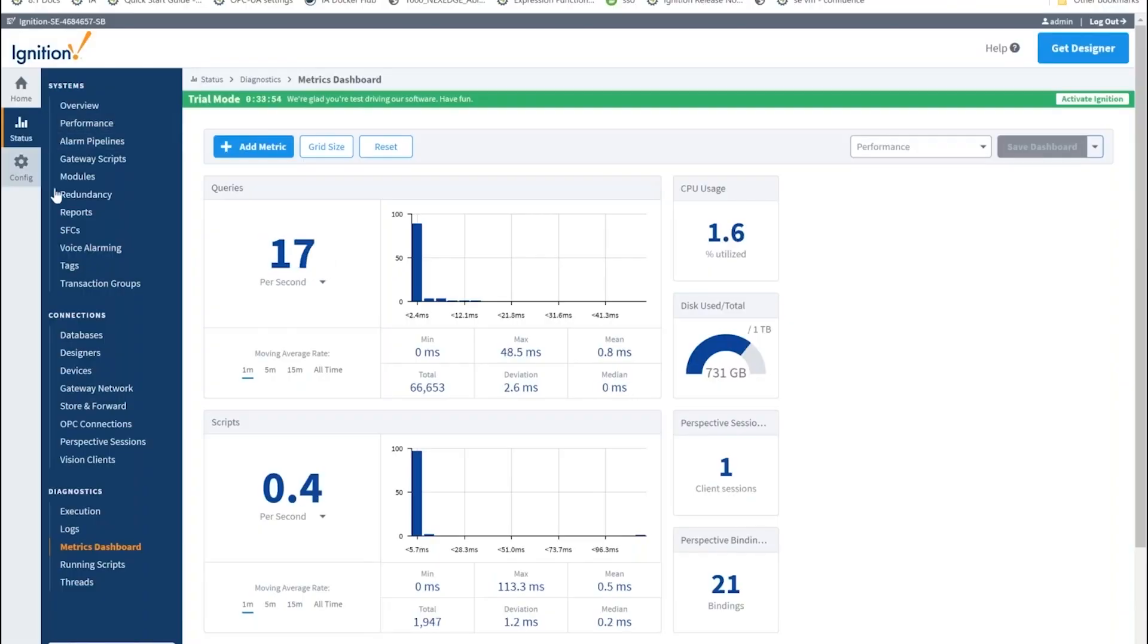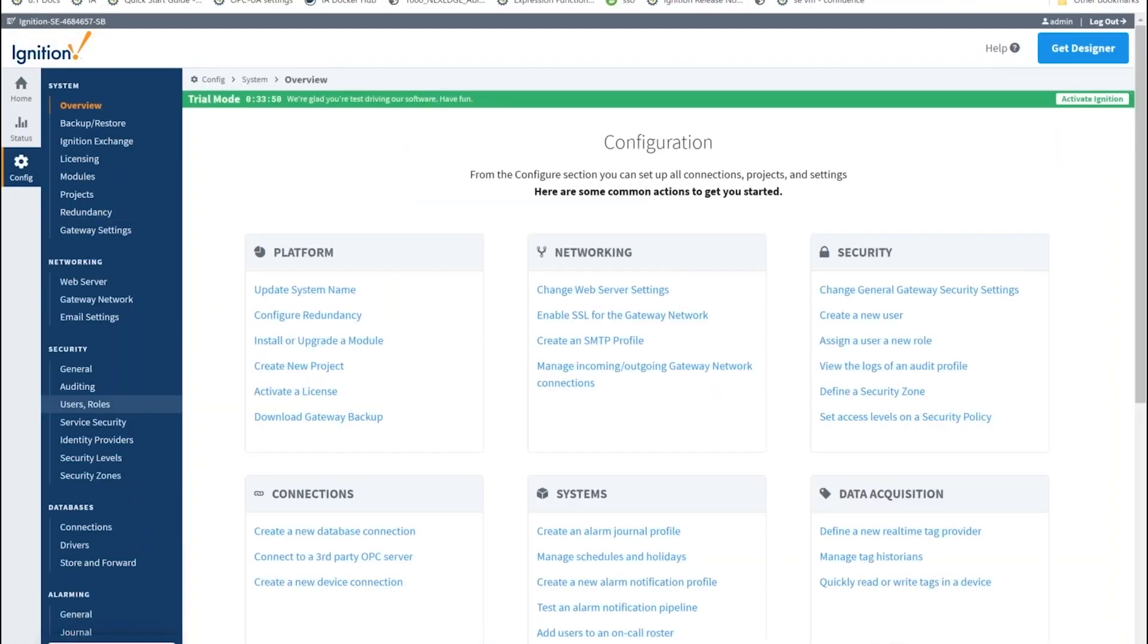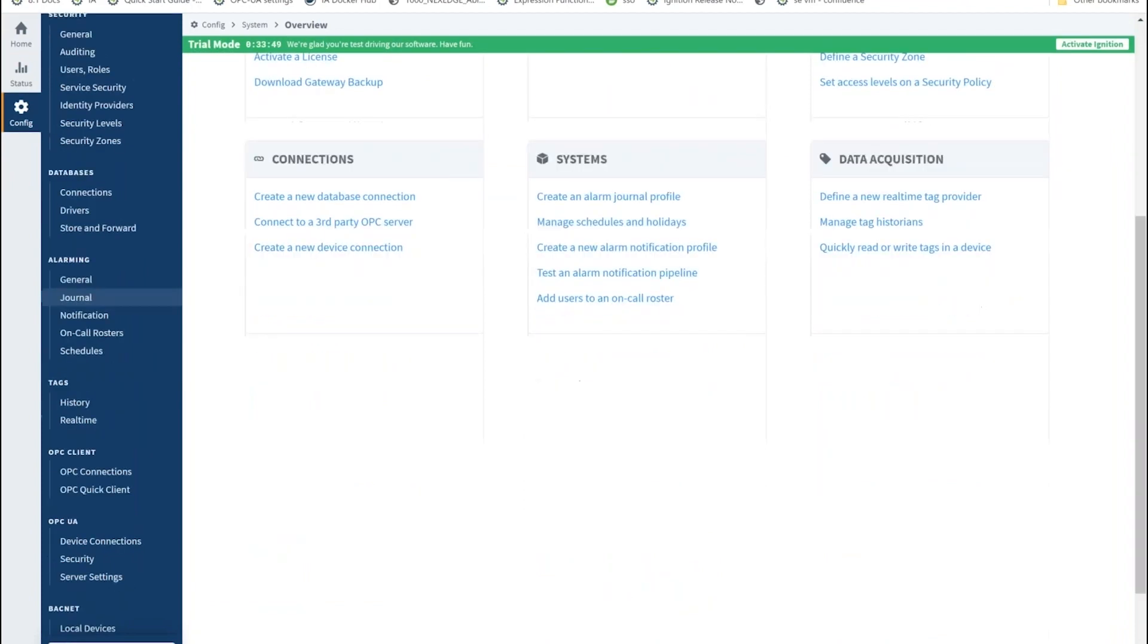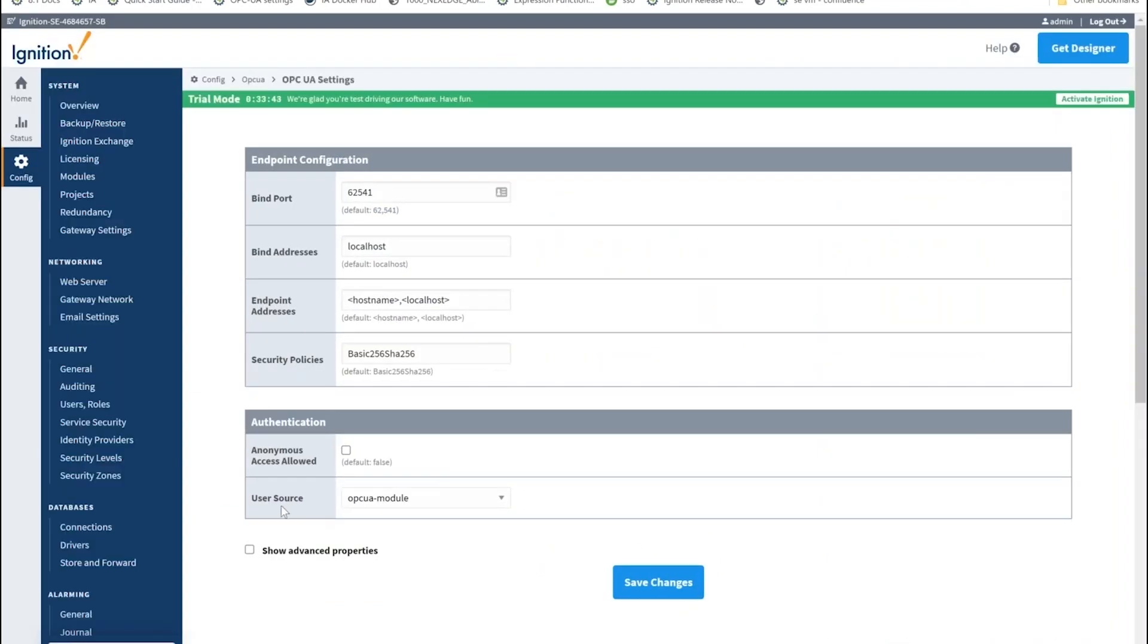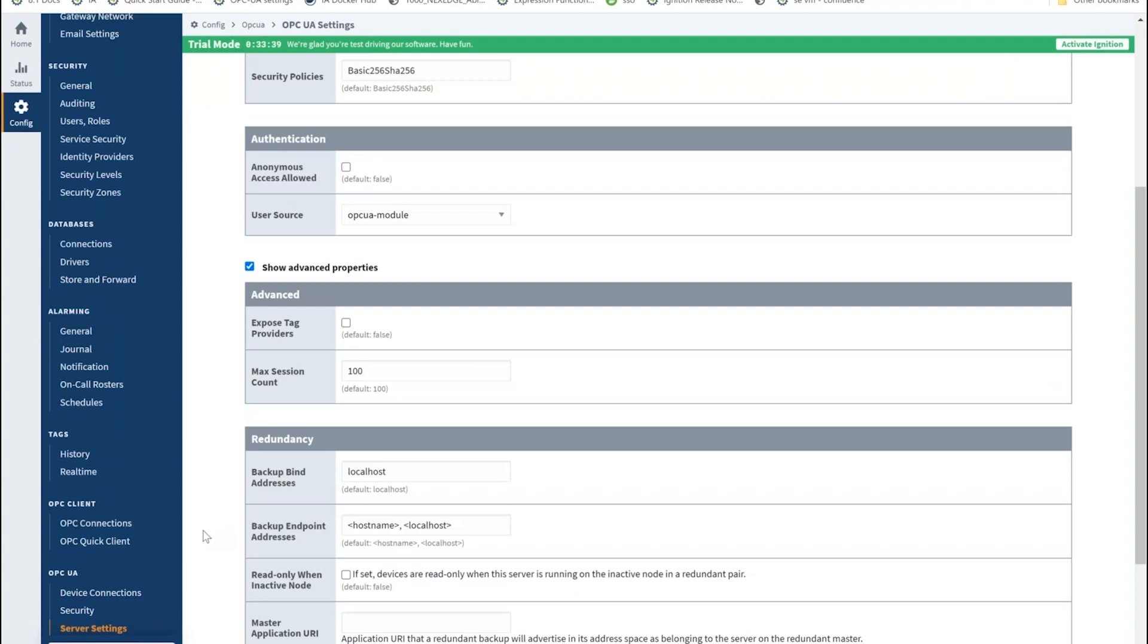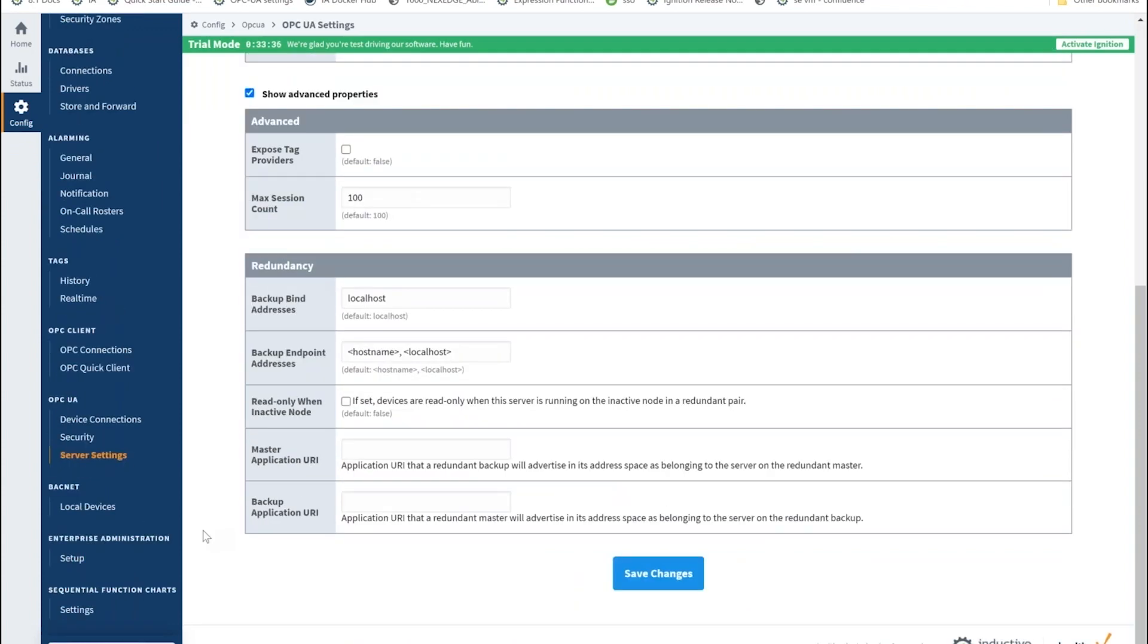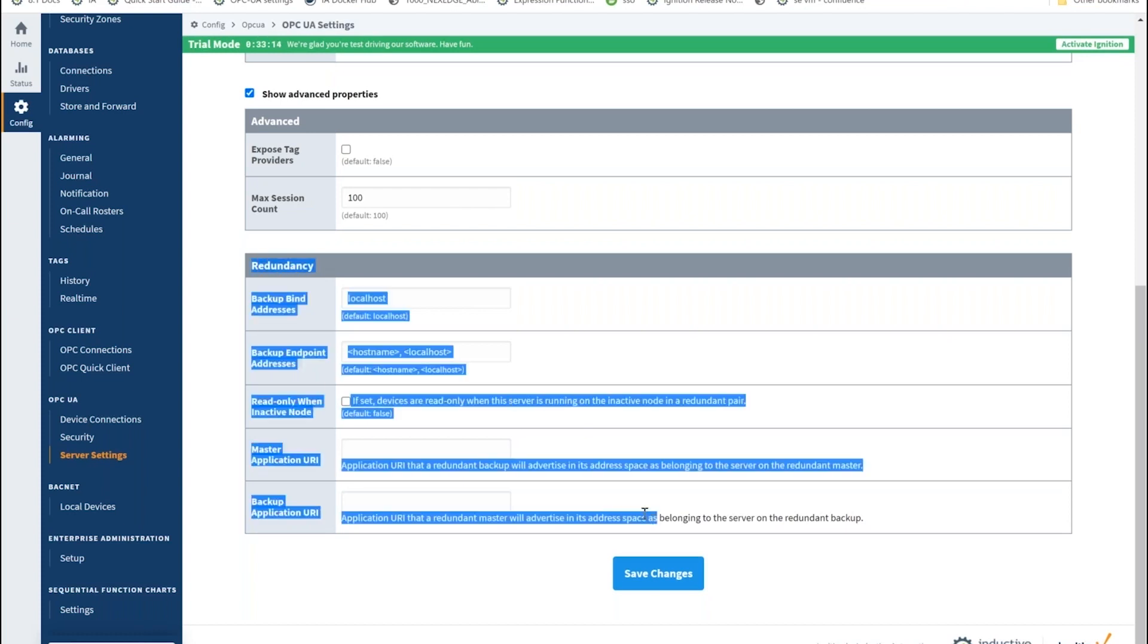The other feature that we've mentioned is the underlying support that may not be necessarily obvious just looking at it. With Ignition we have an OPC UA server built in, and inside that we do have support for redundancy now. Third-party clients can actually connect into Ignition and then be able to fail over to the backup Ignition system with regards to OPC UA. That means you can now fit Ignition into more highly available type of architectures and then reliably fail over to that backup system.